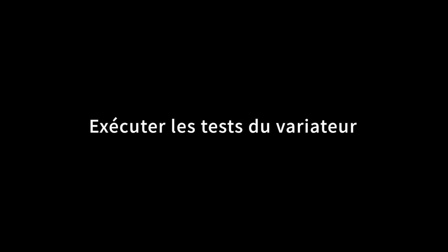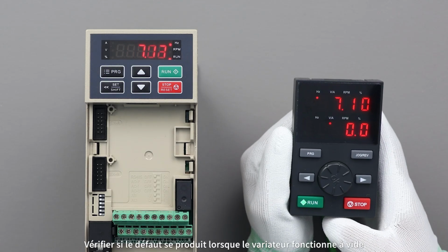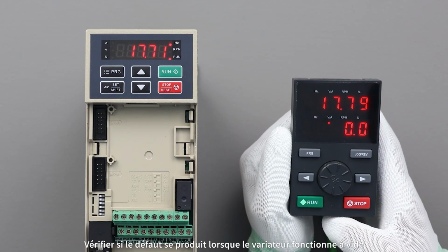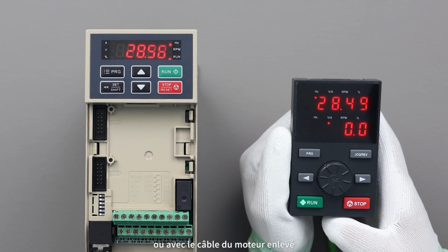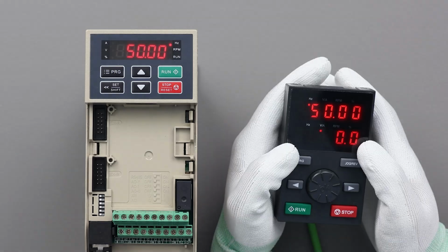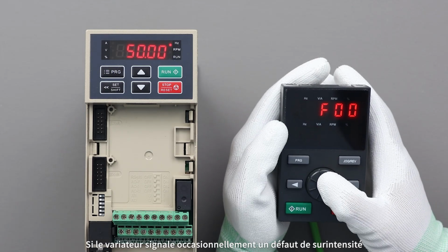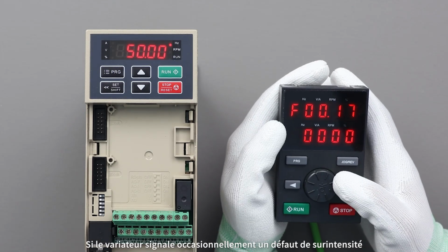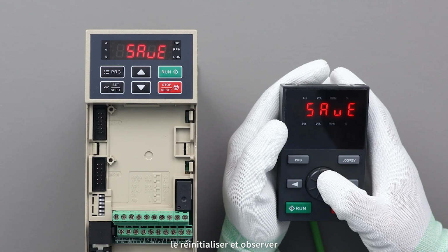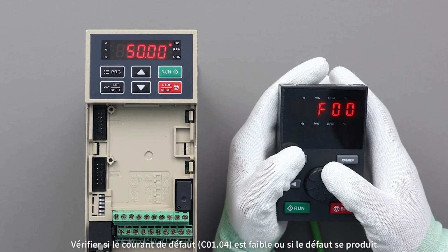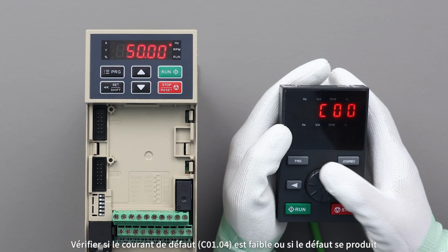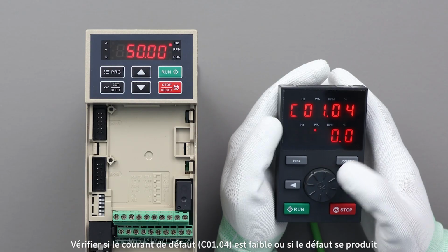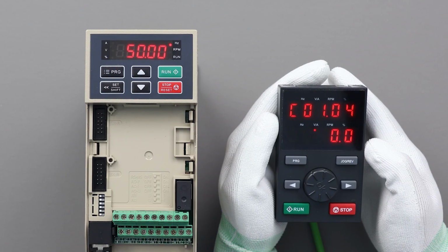Run inverter test. Check if the fault occurs when the inverter runs with no load or with the motor cable removed. Analyze overcurrent faults. If the inverter occasionally reports an overcurrent fault, reset it and observe. Check if the fault current C01.04 is low or if fault occurs.